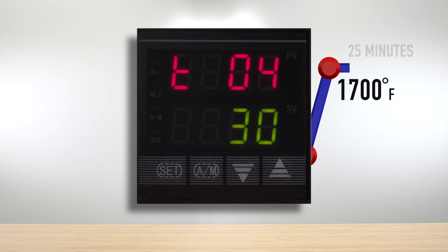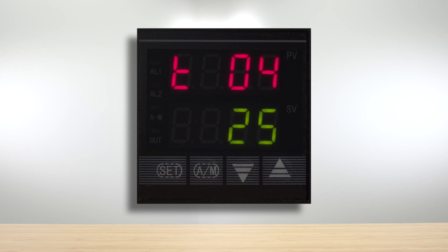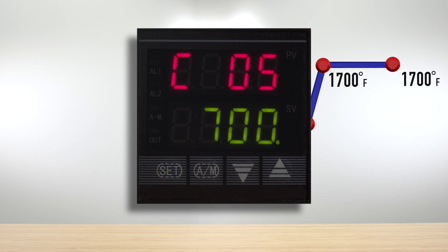So we're going to hit set again. This is going to be a 25 minute burn. So we're going to set this time here to 25 minutes. So we're at 25. Now our next step is also going to be the end of our burn in procedure which is also going to end at 1700 degrees. So we're already at 700 so we're just going to bump the cursor over to the left and change that to a 1.